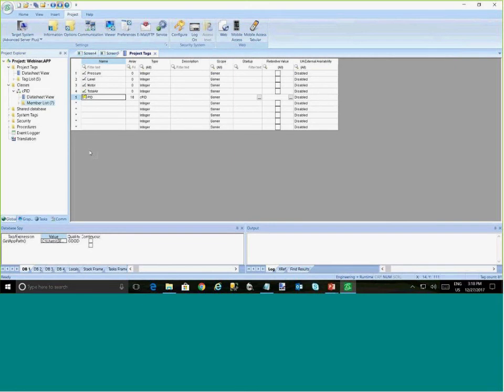Also, in the future, if you want to create new PID loops, you just increase the number of arrays. If you want to create new members to the PIDs, you just create a new member to the class once. And it enforces consistency across the whole project. And each one of those tags are still holding an individual value. For example, I can use PID index 5 dot set point. This is the set point for the PID number 5. I can have PID index 6 dot set point. It's a different value. Can have 10 here and 20 here, and so on and so forth.